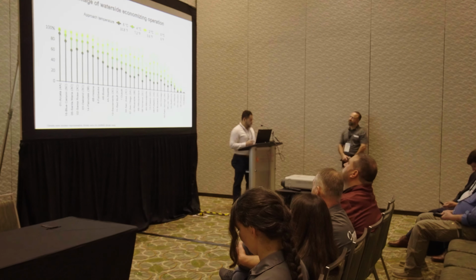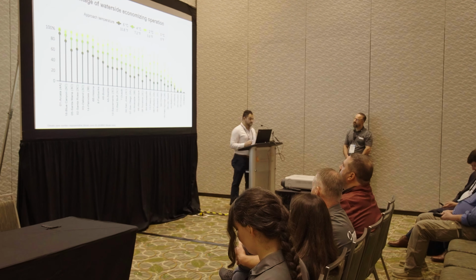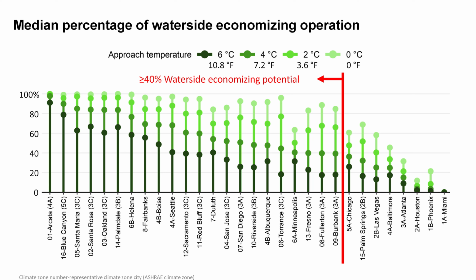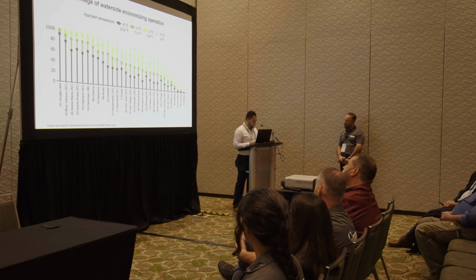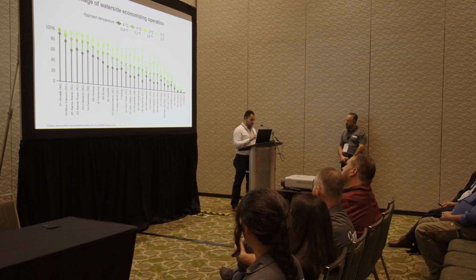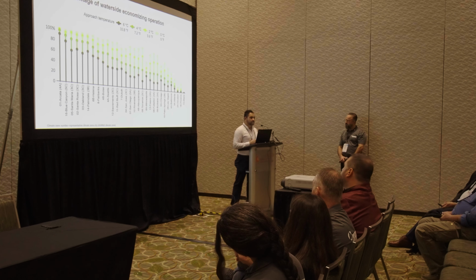And so the main results show that waterside economizing is possible in many US cities. In this plot, you see the proportion of hours that the cooling tower is able to provide the design chilled water temperatures for the design variant. Let me repeat that again. What you see here is a proportion of hours that the cooling tower is able to provide the supply water temperature for the radiant system design that we modeled. And this is divided by the total hours that the radiant system is able to operate in the cooling season.